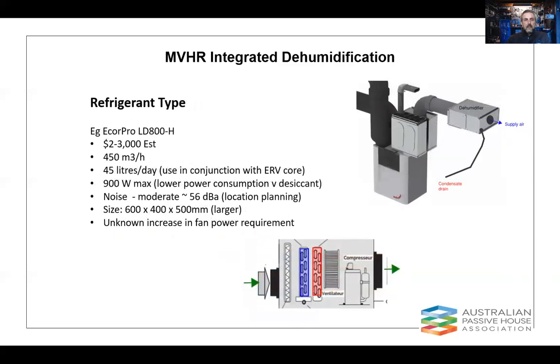If we look at the next option there, it's the refrigerant type, and this is probably classically what people have seen a little more often. It is basically the same thing as a split system, but you'll note there it's got two coils. Essentially, that type of dehumidification occurs by getting the air temp down really low, and when it's low, it can't hold much moisture. That moisture falls to the bottom of that coil, and you'll note top right hand shows a condensate drain, but we then use the shaded red coil to bring the temperature back up to what it originally was. So in this instance, we can get dehumidification, but we're not getting cooling at the same time, which is what we want.